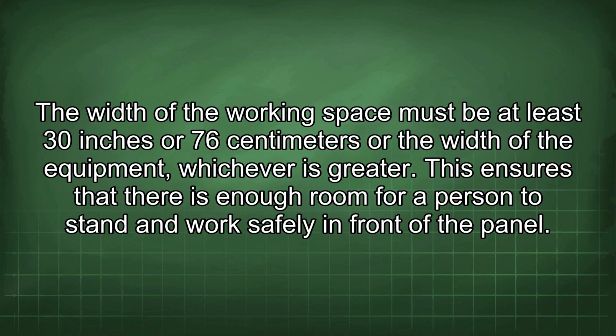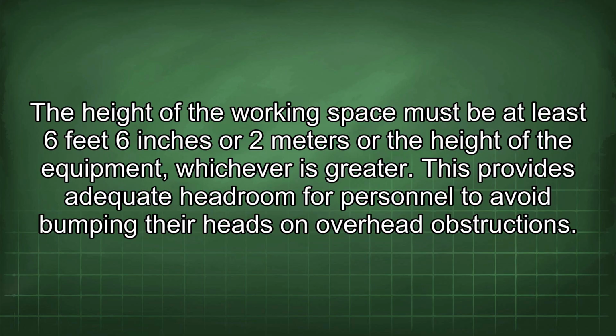The width of the working space must be at least 30 inches or 76 centimeters, or the width of the equipment, whichever is greater. This ensures that there is enough room for a person to stand and work safely in front of the panel. The height of the working space must be at least 6 feet 6 inches or 2 meters, or the height of the equipment, whichever is greater. This provides adequate headroom for personnel to avoid bumping their heads on overhead obstructions.